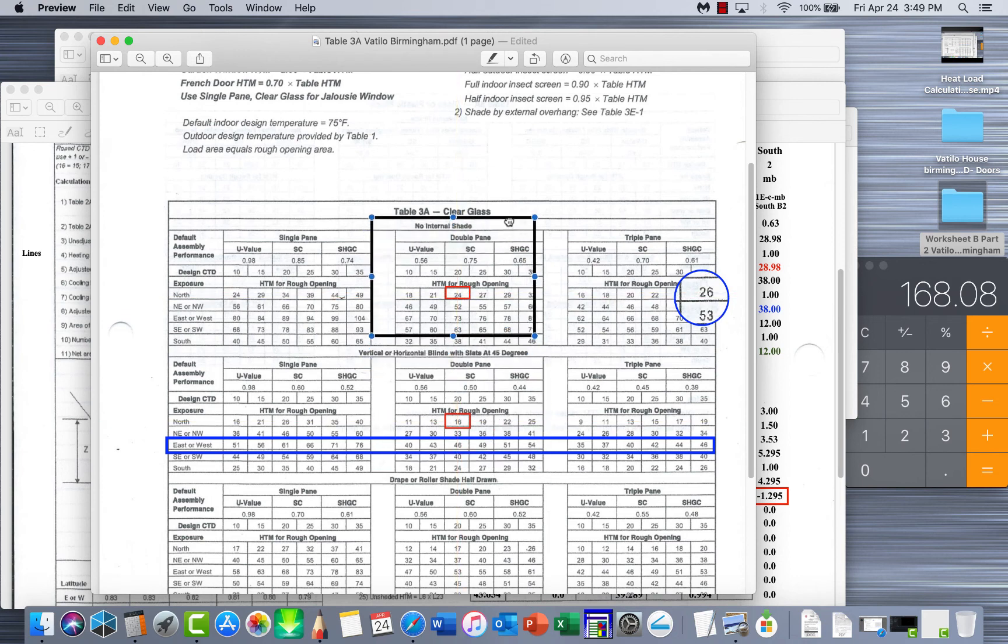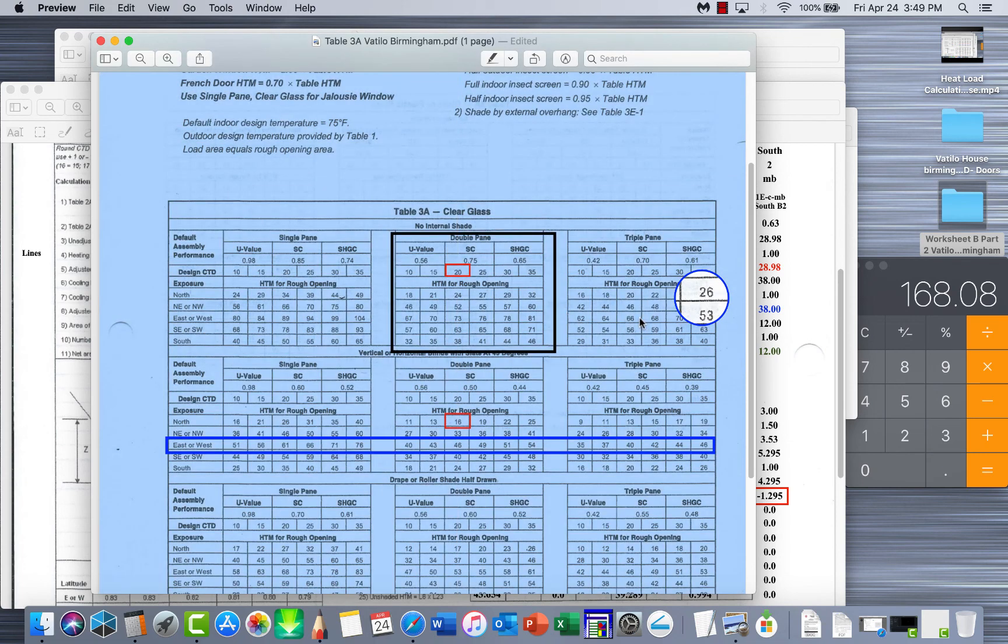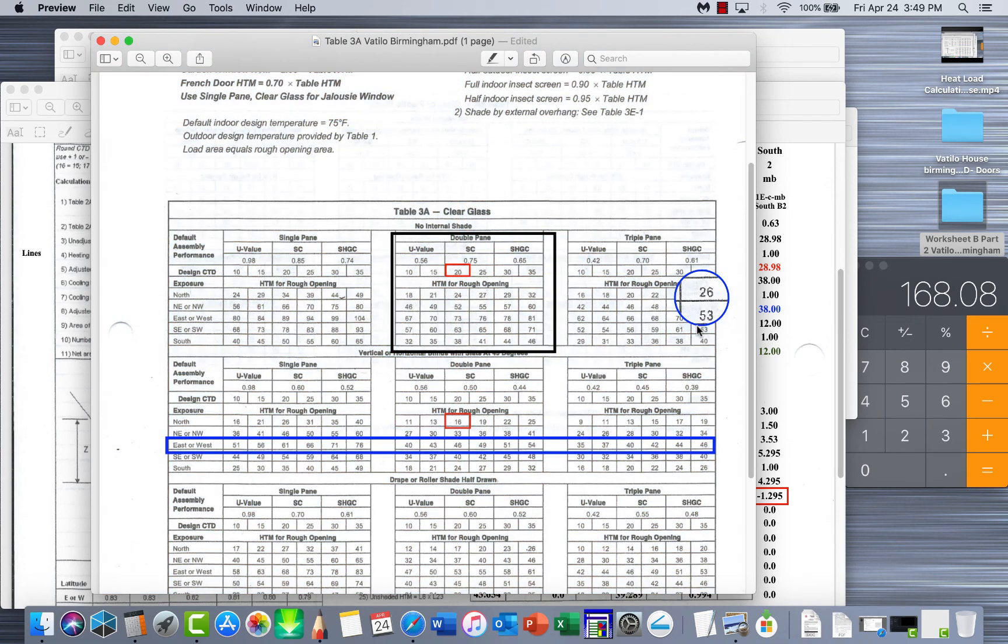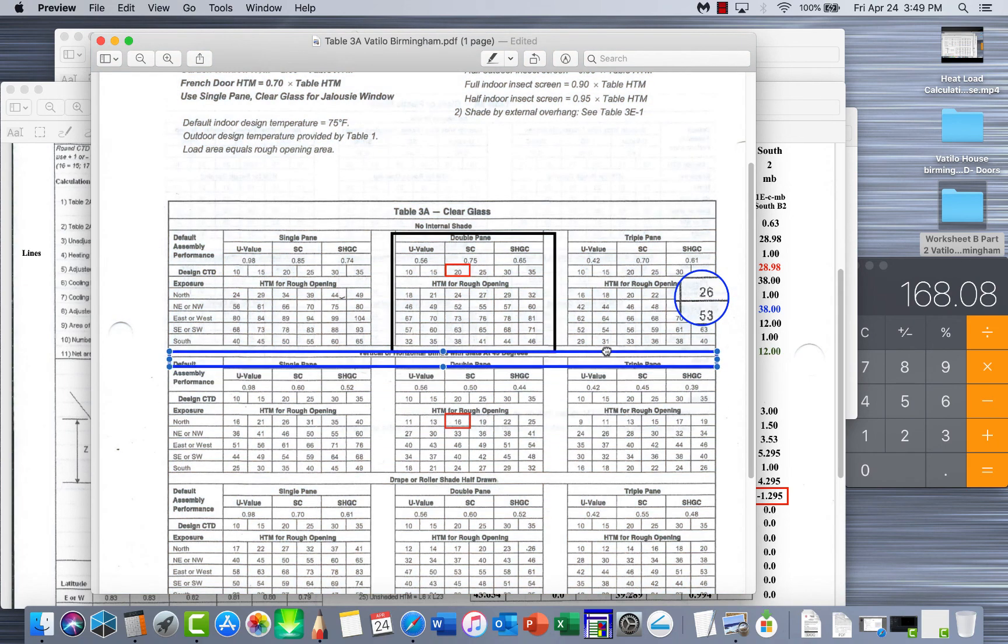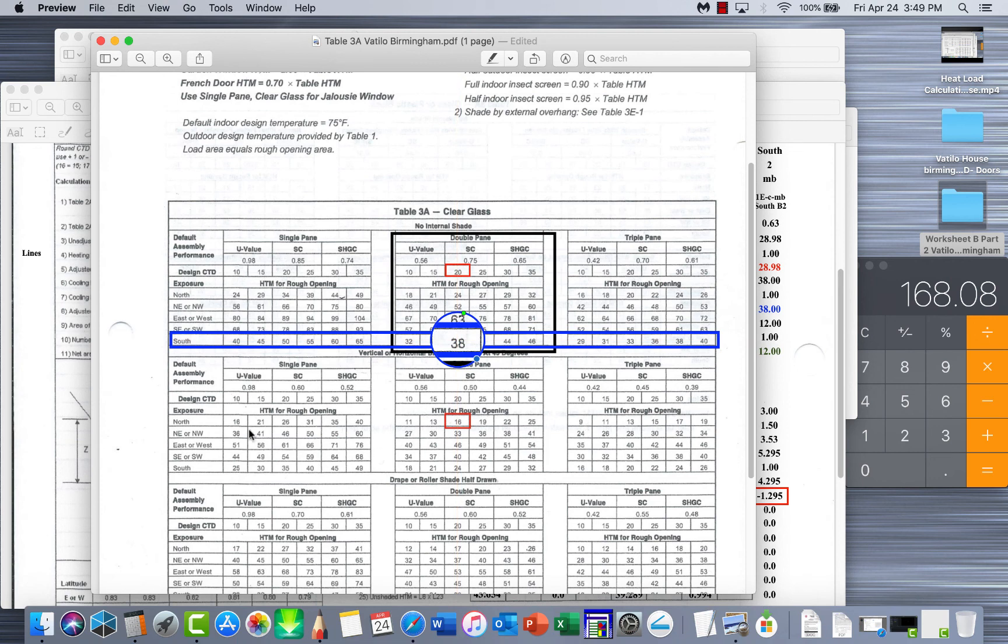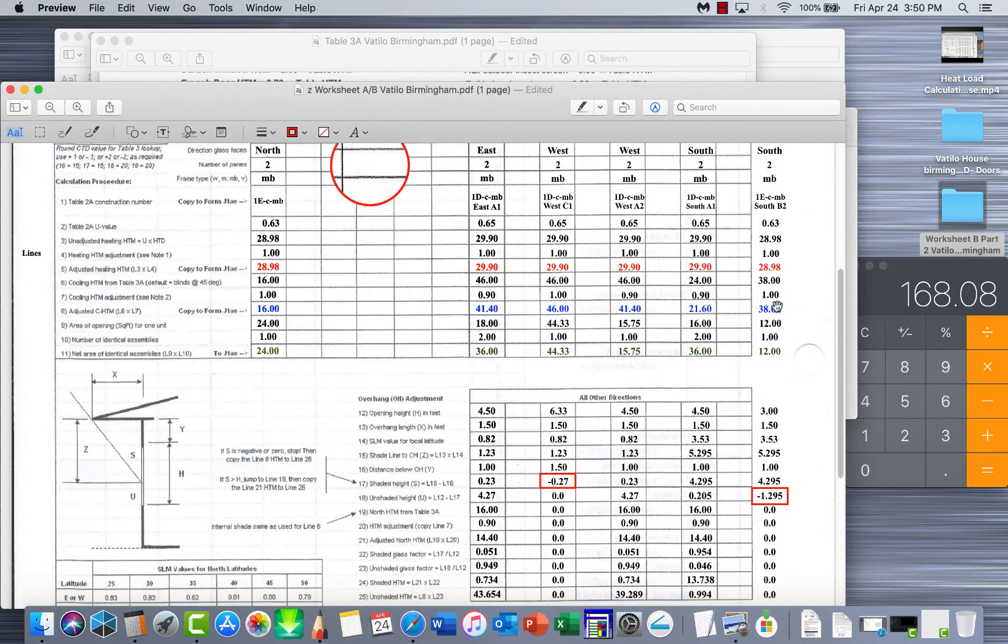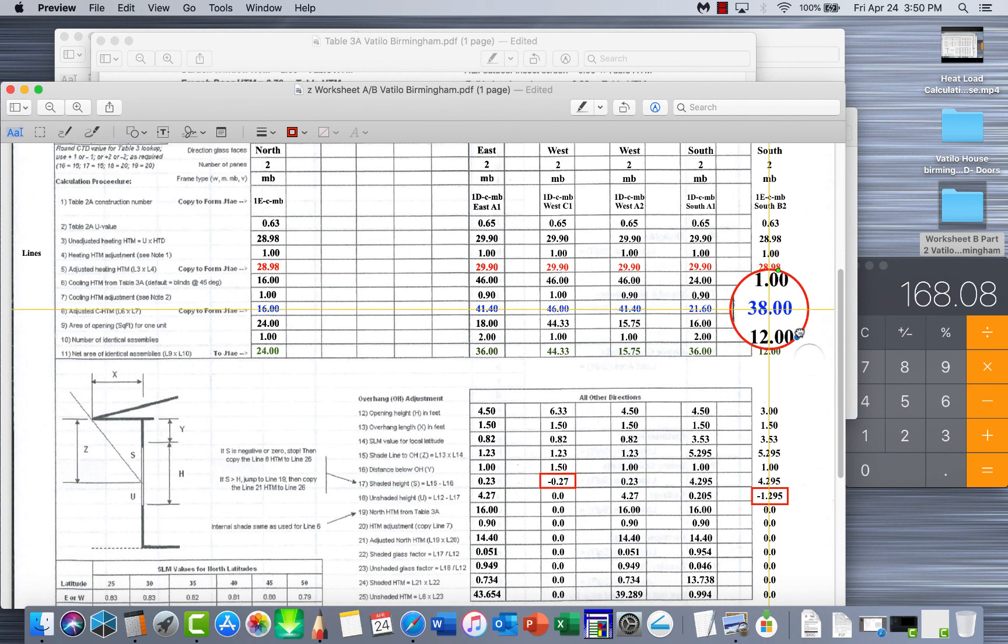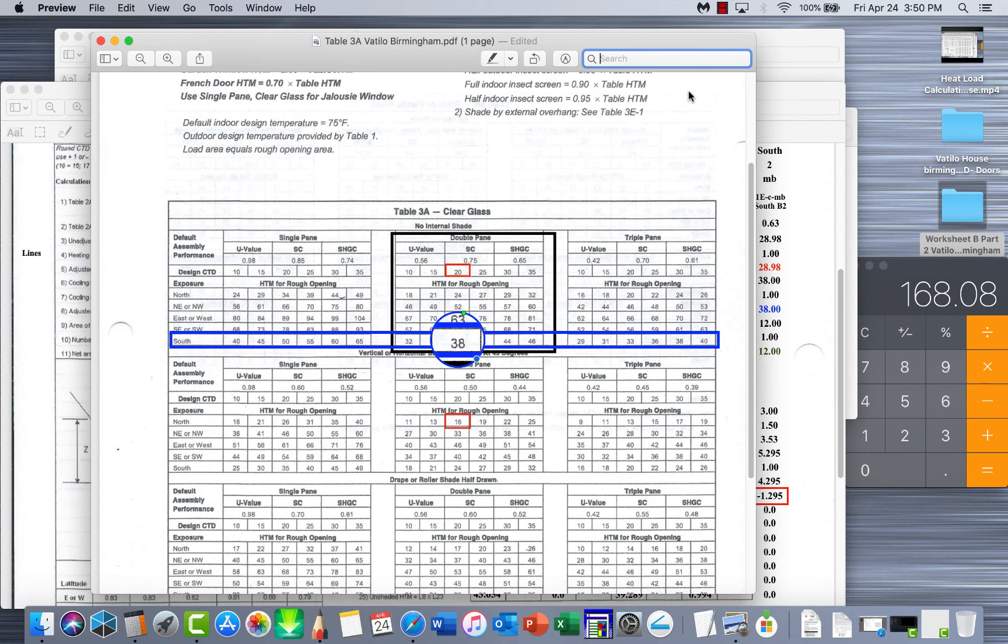A daylight window has no internal shade. So when you do this calculation, you would do this one right here. Of course, our CTD was 20. It's a southerly window, so that's going to put it on this line down here. So that means the number that you would actually use for this window since there's no internal shade would be that right there at 38. Don't use this window down here because this is calculating it with blinds. And like I said, as you can see, the numbers are very different - 24 versus 38. So that's why we ended up with this 38 right here. So just make sure you're using the correct charts and you're reading your information correctly. But that's for that one window. This is that one window that wasn't shown, it was just understood that it was completed because it was on there, J1AE. But this was actually on this one. So that should complete you up on this.